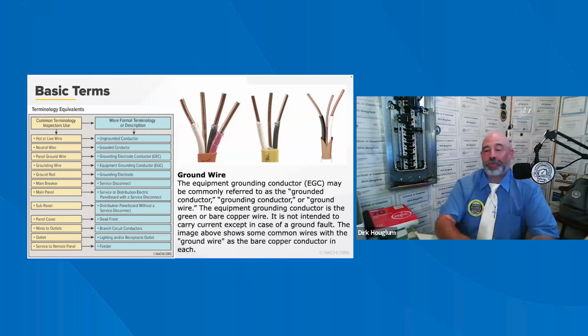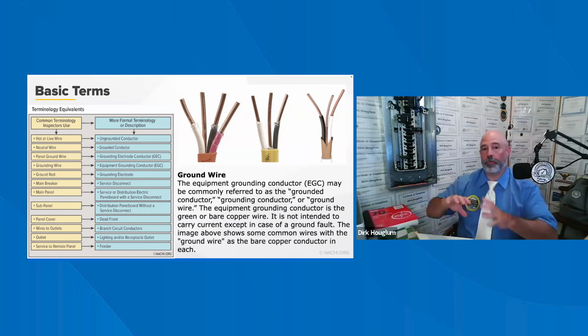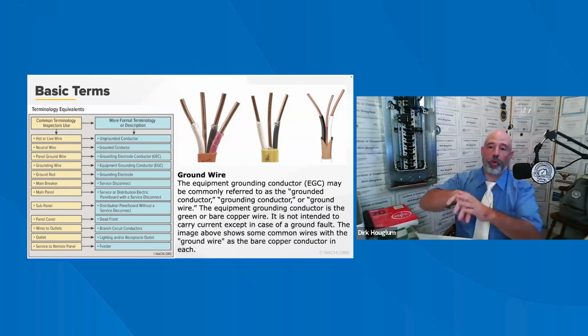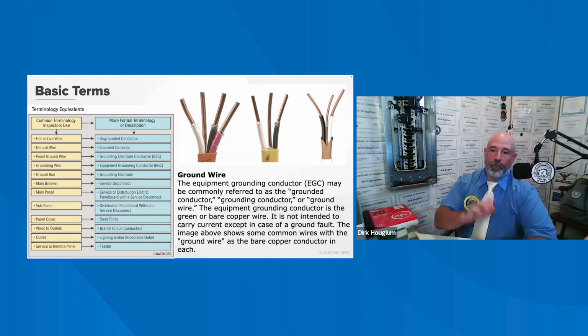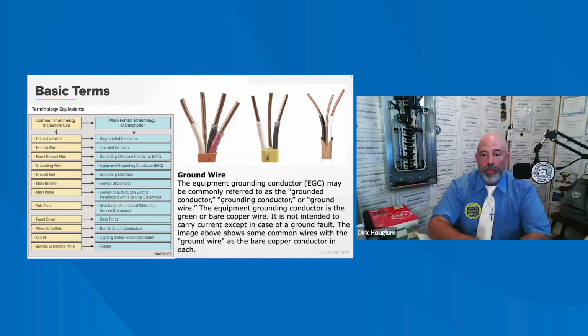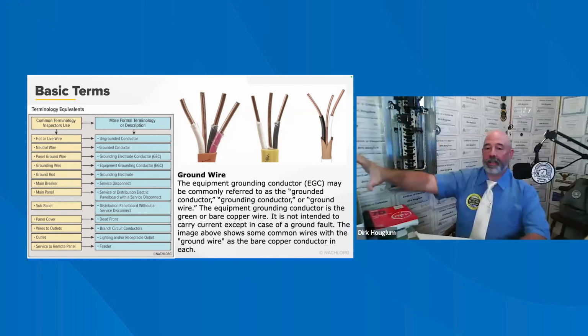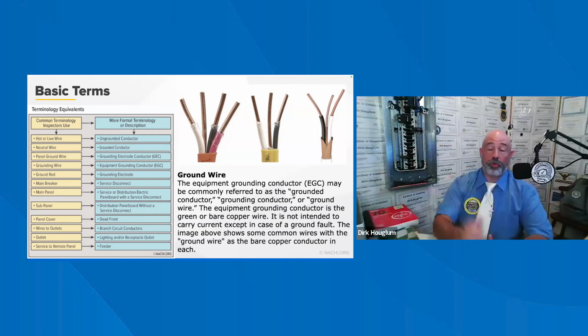A line refers to the line that's actually going into the equipment, into the power equipment and the terminal or whatever it is. A load refers to the outgoing power. So you got your line in and then you got your load that goes over. Your main breaker is what disconnects the entire electricity from the house. Normally now these main breakers are on the outside of the house, not on the inside anymore, because if there was a fire, the fire department can quickly shut it off.